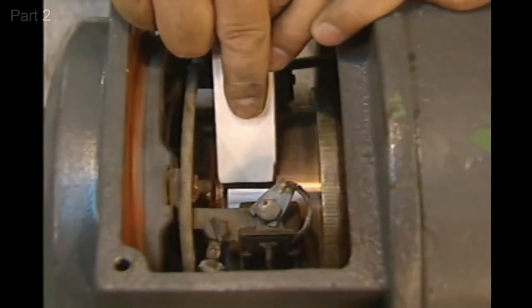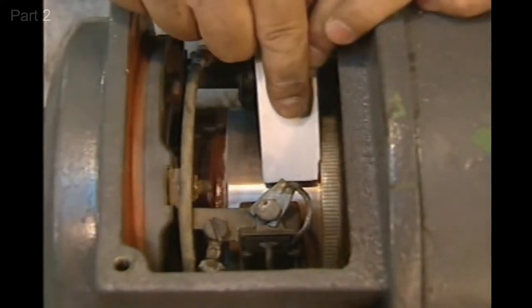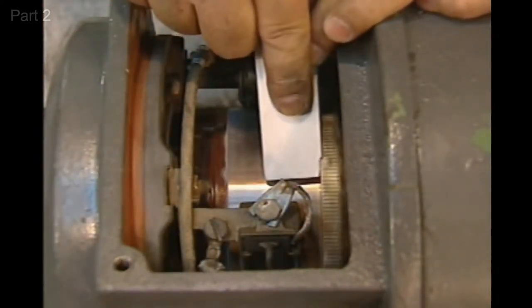When the motor is running, the commutator's surface can be cleaned with a canvas wiper or a commutator stone to remove dirt and other contaminants without removing the protective film.